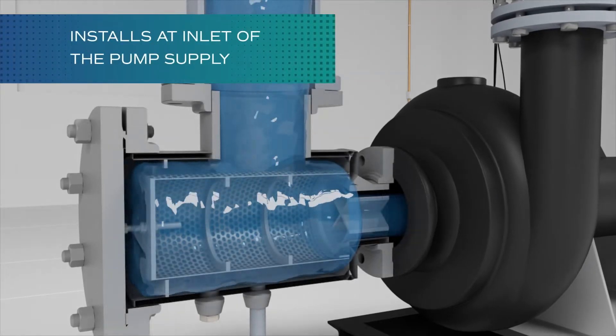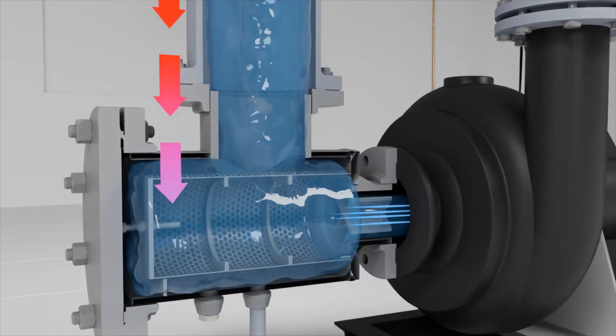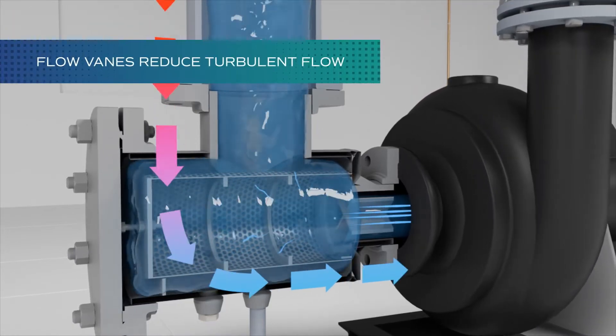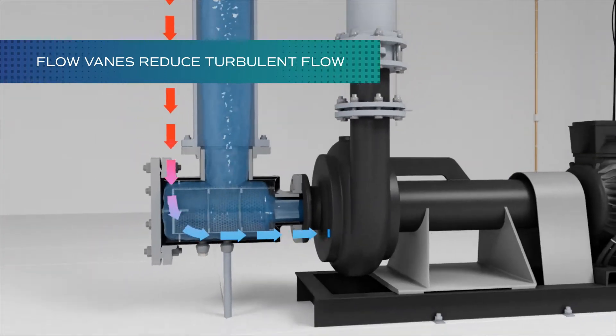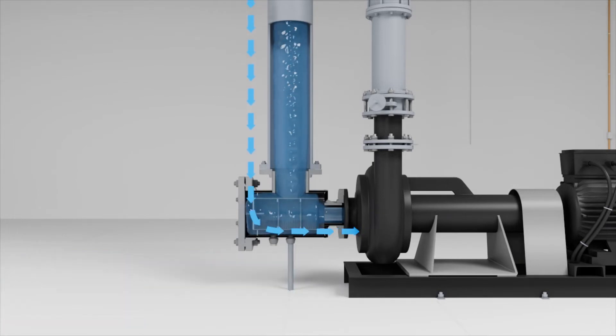Installed at the inlet of the pump, the Suction Diffuser features flow vanes, which provide flow straightening that reduces turbulent flow and the potential for cavitation. This effect increases the efficiency of the pump, resulting in overall cost savings and extending the life of the pump.